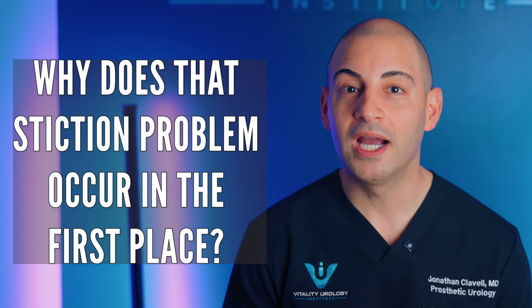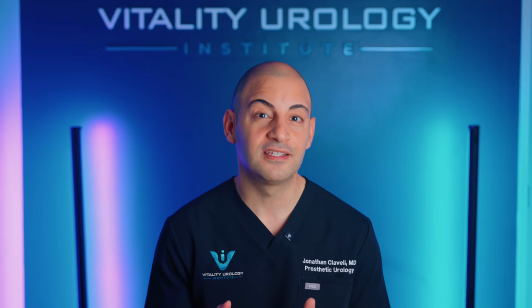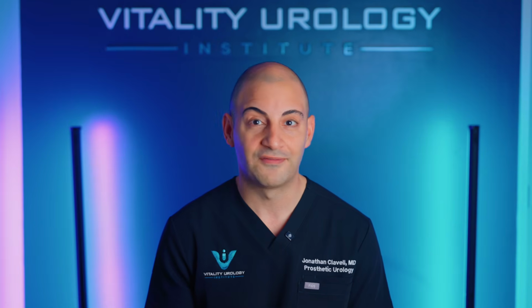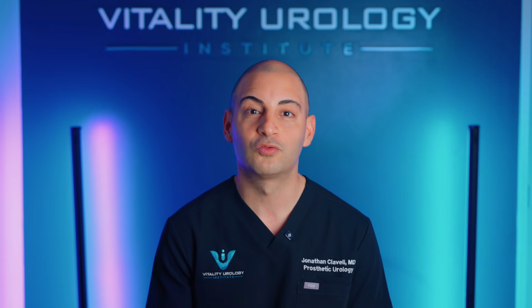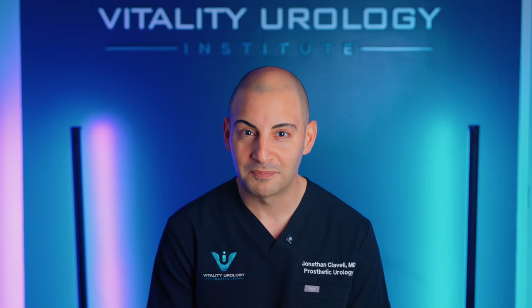Now, you might be wondering, why does the Stiction problem occur in the first place? Well, the MS pump has both the inflation and deflation mechanisms within the same valve, and sometimes one of the components that allows for this valve to be one way and intended to prevent autoinflation can become fixed in the deflated position, and therefore it can prevent the transfer of fluid among the reservoir, pump, and cylinders. Some believe that this might be a reason for which the sticky pump occurs. However, there is no research that validates this as a true cause, and this remains just a theory. If you wish to learn how to best inflate and deflate your AMS 700 MS pump, we recommend you watch our YouTube video, link above.